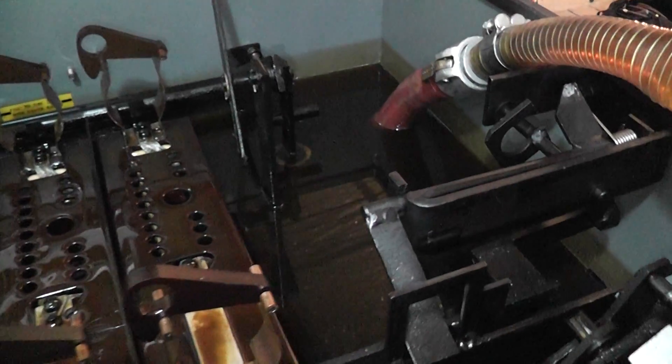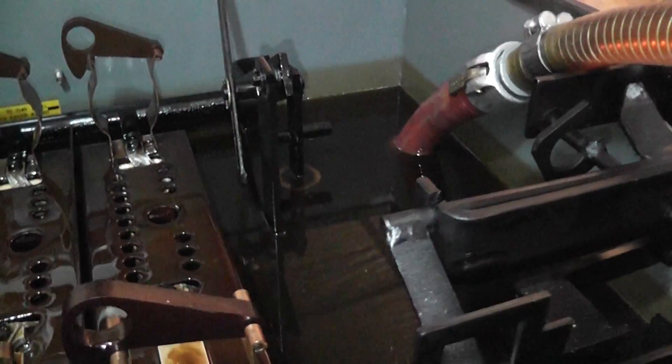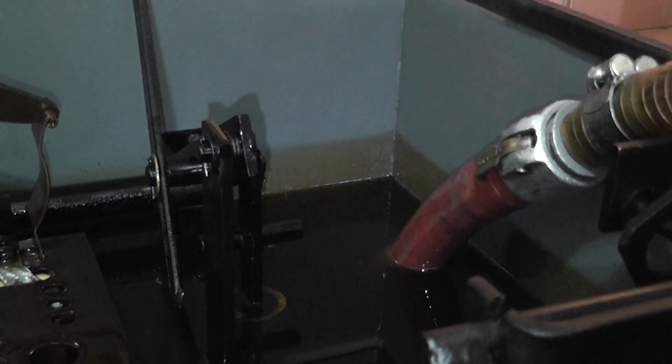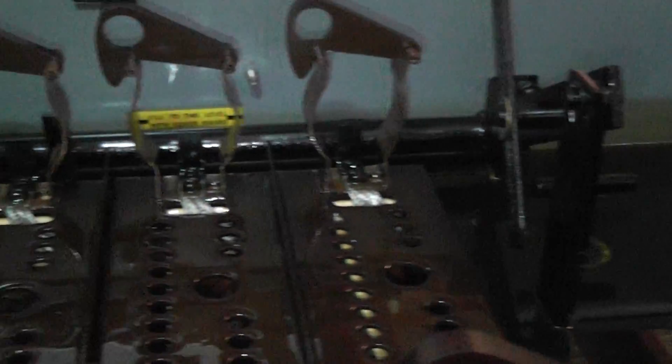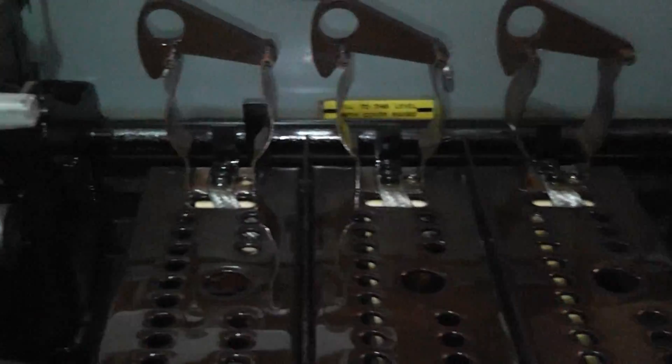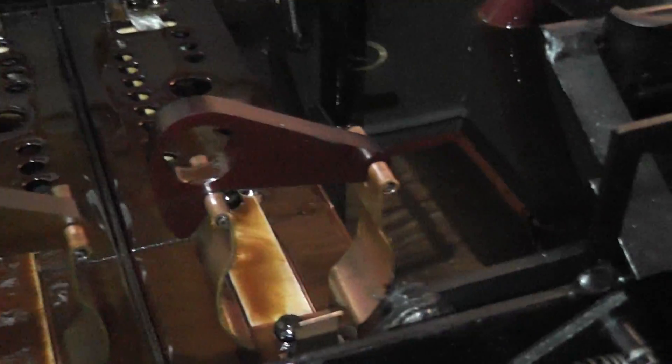We're just draining out the oil at the moment. As you can see on the side, it was very dirty oil, sludge oil. So this switch was definitely due for maintenance. When we're done, we're going to rinse it into some clean oil and then fill it up to the appropriate level.